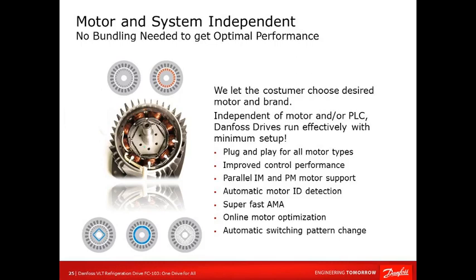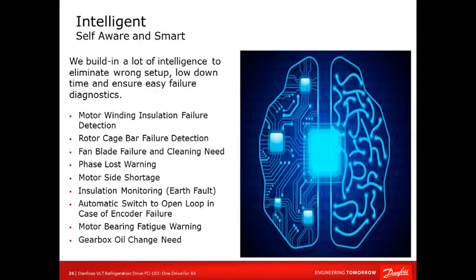So the advantage, again, Danfoss can operate and it's an open device and shake hands with all different types of motors. You might start hearing about permanent magnet motors. Danfoss actually makes one for the food and beverage on the packaging side. So Danfoss, just to assure you, has the capability to actually control PM motors as well as just a standard AC motor. Again, you'll learn maybe, or you've read, people are going to PM motors as just a higher efficient motor. But again, good news is not a problem for Danfoss. So we can do that, and we are doing that on a lot of OEM equipment. It'll be our VFD with somebody's PM motor.